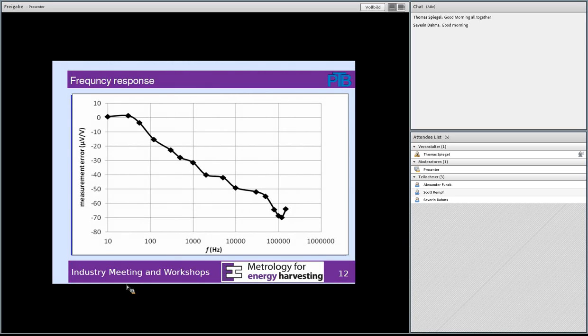But if you look here at the scale, this is microvolts per volt, so other people call it parts per million. And it is well below 100 parts per million, which was also the goal in our project. We tried to measure everything in the order of 10 to the minus 4, which is 100 microvolts per volt in this case. And the other thing is, if you can calibrate something - okay, here are no uncertainty bars - you can also correct for it if that should be necessary. So this is not really a drawback in performance.